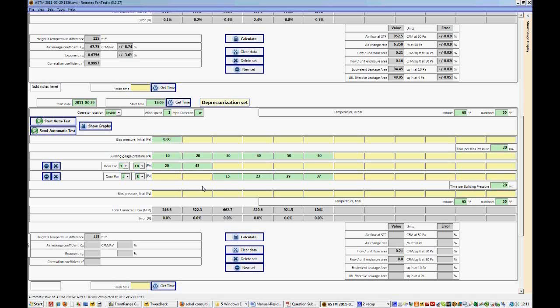One good tip when running a manual test is, before you start testing, select a range, for instance B range which is in the middle, and then set the fan up to go from, to go up to 10 pascals and then up to 60 pascals and see if you can reach both ends of the range. If you can, then you won't have to worry about changing the ranges through the test. If you can't, then try another range to see if you can actually achieve the full range of building test pressures or target pressures before you start the test. This will make things a little bit easier for you.